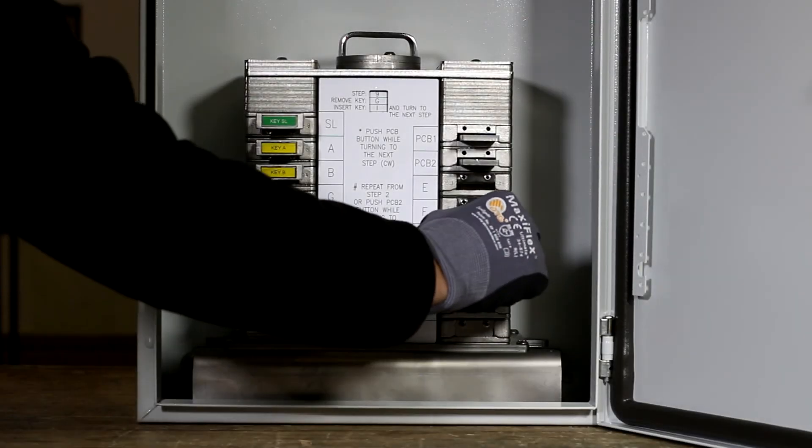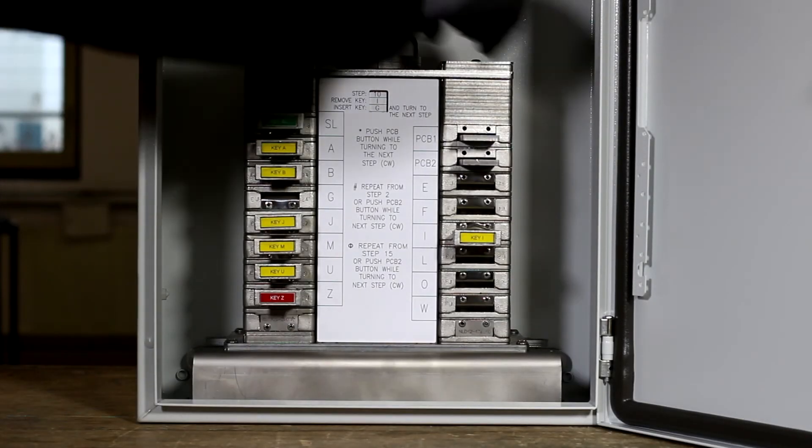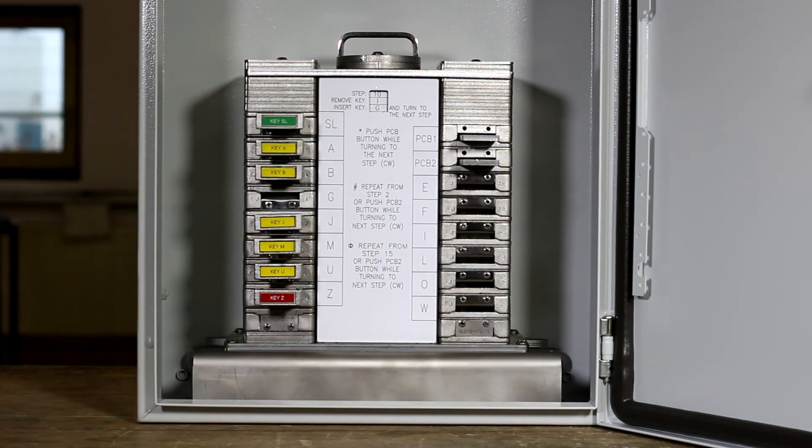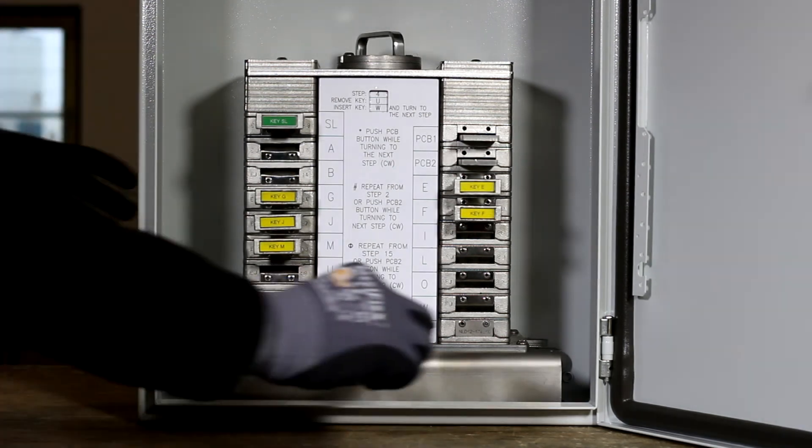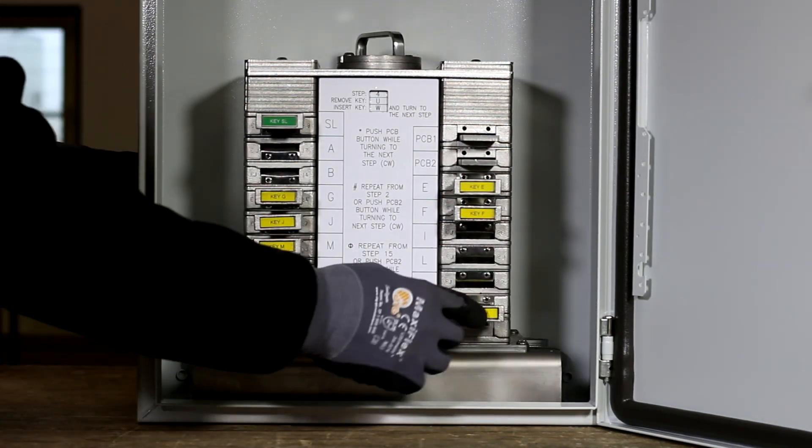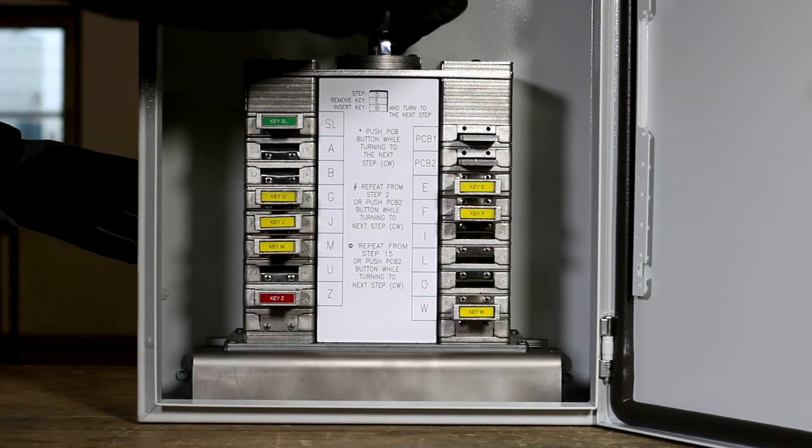The MPCU can return the same key that was entered, meaning the previous steps must be reversed before the next part of the sequence can be initiated. The MPCU can also release another key, meaning the next valve must now be operated.